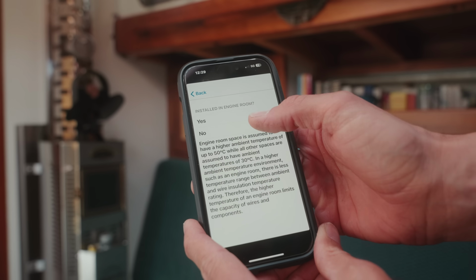Then you indicate if it's installed in an engine room or not, because higher temperature affects that, and also how many wires are in that bundle. It makes a difference if it's only one cable going somewhere, or if it's in a conduit with 20 others that also accumulate heat.